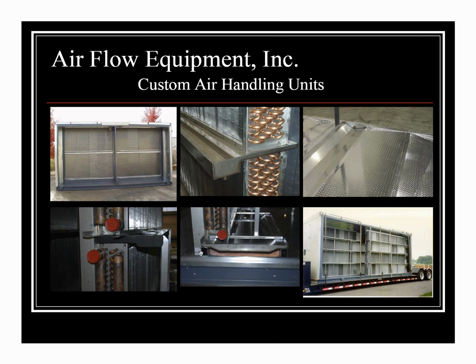A couple other things that we think can be neat. On this bottom picture, you're seeing a coil that's actually raised up above the floor of the base of the unit. That's to help provide trapping space. Maybe it's an indoor unit, there's no housekeeping pad, the unit's going to be set directly on the floor, and you're concerned about providing trap space. How are we going to have enough space to trap it? If we're involved in the design up front and are aware of that, we can design the unit so that we physically raise the coil inside of the unit, providing the space necessary for the traps, and you're good to go, and that's no longer a concern.